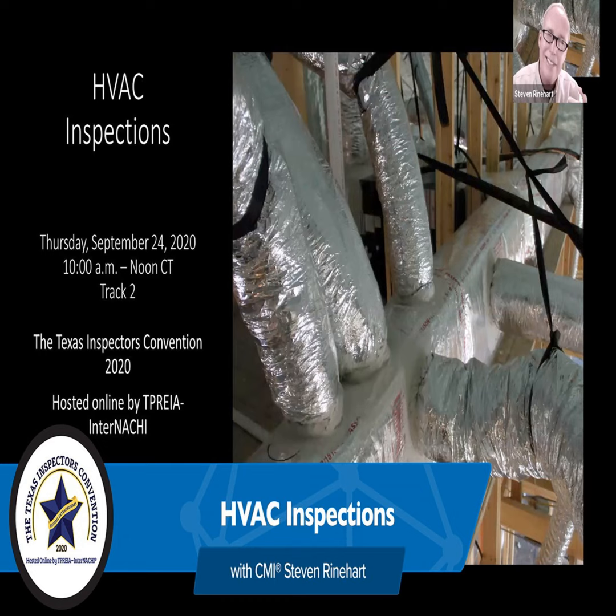it's an atmospheric burner. There's no draft ventilation, there's no powered ventilator. It draws air for combustion in those louvers, and it mixes it as it goes up the big opening. It kind of pulls air from this closet and goes up with it. In a perfect world, by itself, with no changes in pressure, this works. But there's a couple of things to think about. You see one of these, it's old. Things you can't see is that burner.